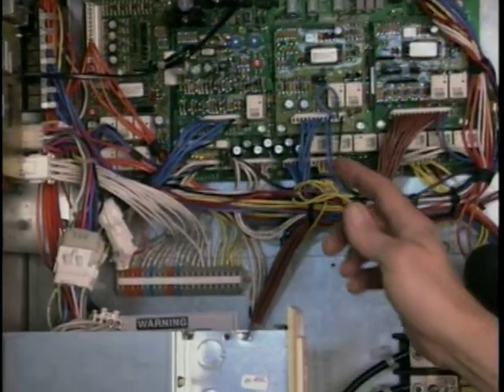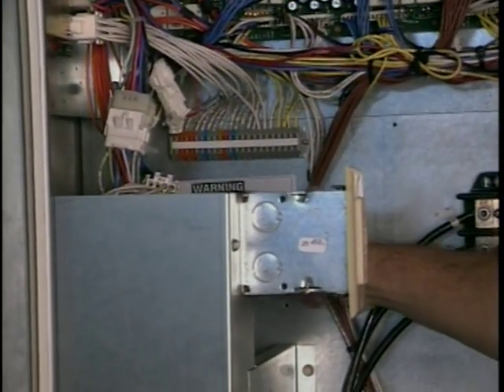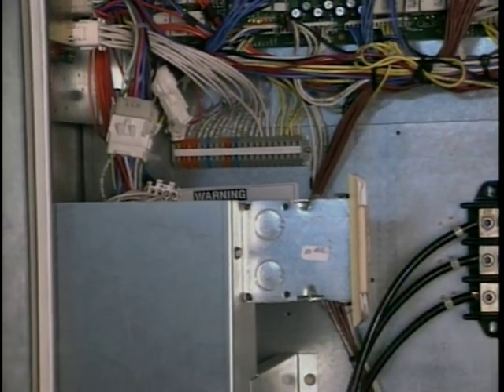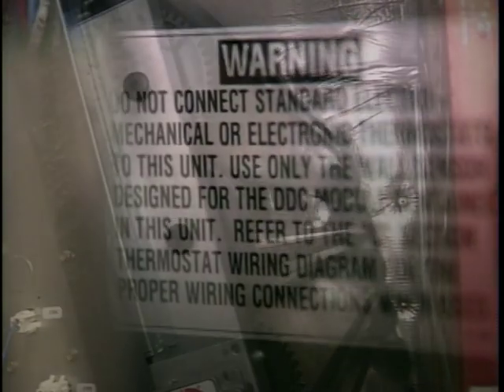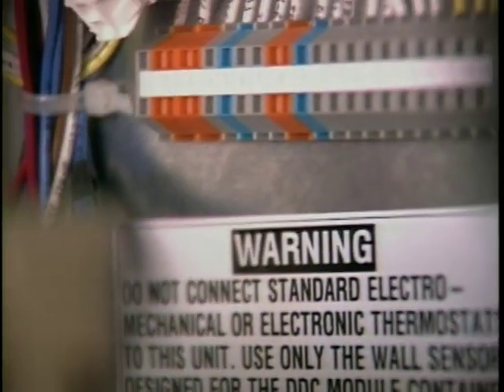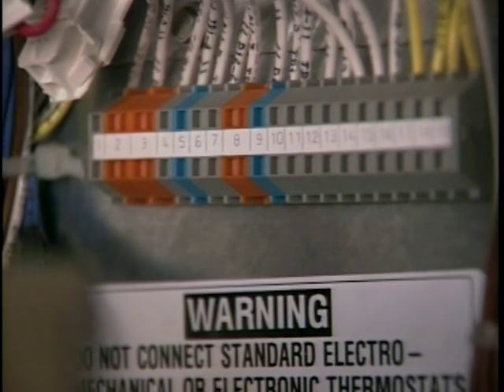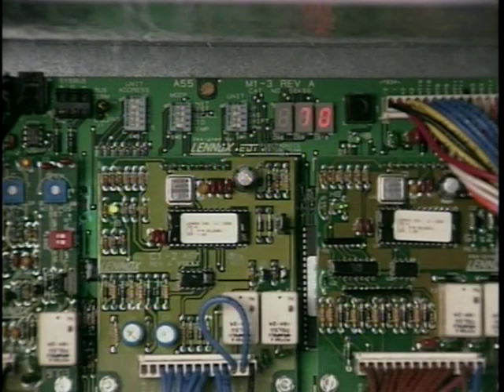This will cause the indoor fan to run continuously. Put a jumper on TB1 from terminal 8 to terminal 9. This will cause the outside dampers to open to the minimum position when the unit is turned on. The presence of the jumper on terminals 8 and 9 is read when the disconnect is turned on. If this jumper is not present, the IMC will prevent the dampers from opening for 30 minutes during the first heating or cooling cycle.